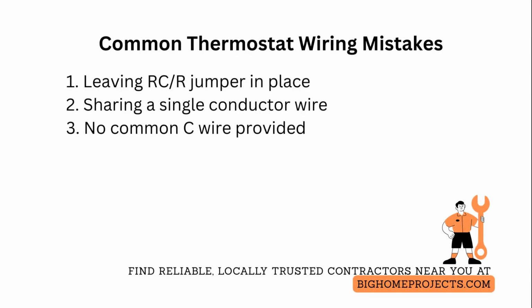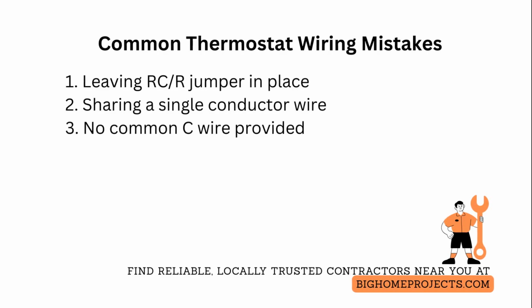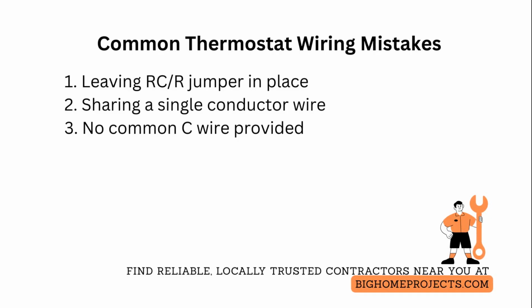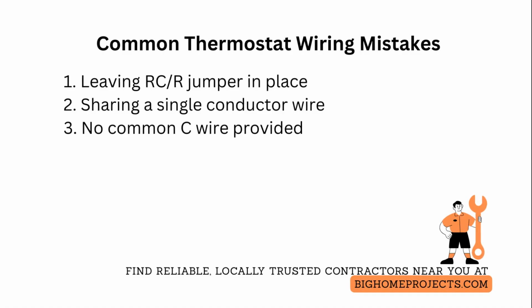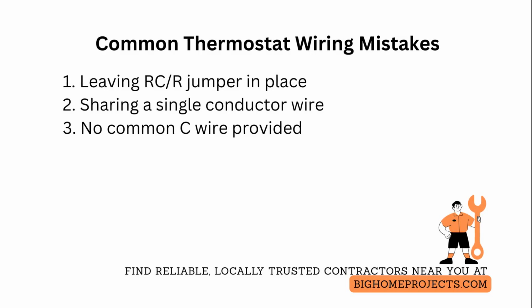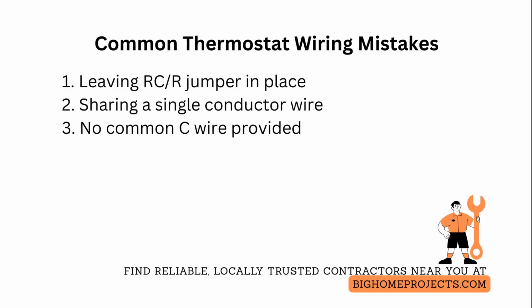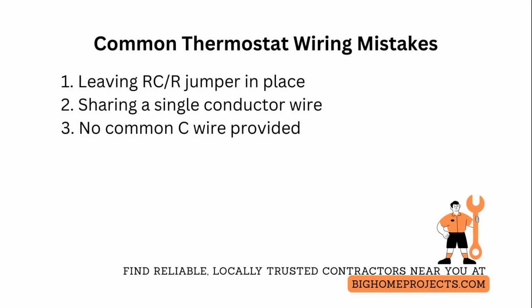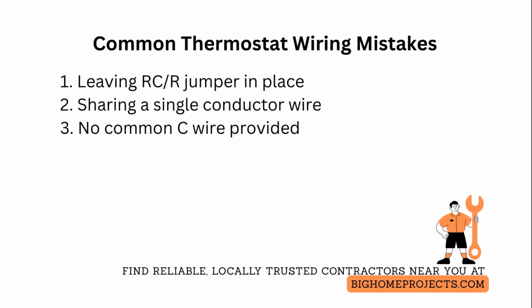One of the biggest mistakes is leaving the RC/R jumper in place when both the boiler and the air conditioner are on separate transformers, which causes a backfeed and can damage transformers or trip fuses. Fix this by removing the jumper and installing an isolation relay or using a thermostat interface rated for dual transformer systems. Another common error is sharing a single conductor for both systems calls by reusing a wire, causing unpredictable behavior. Fix it by running an extra conductor or using a properly rated zone control or relay.